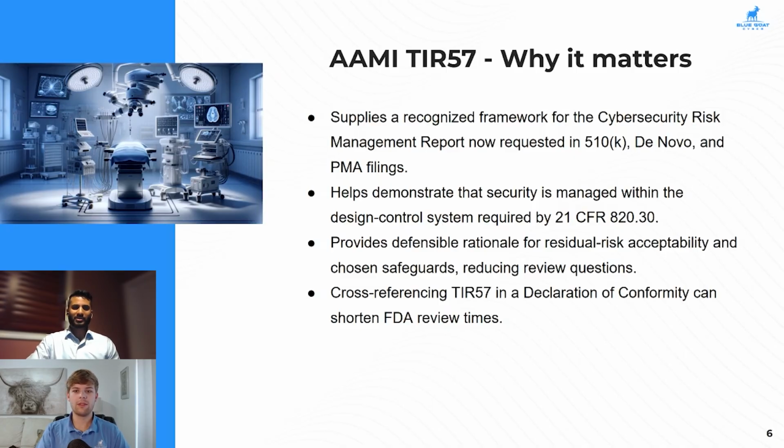Absolutely. And I think it's in a sense no different than all the other frameworks, in the sense that you need to start early on. You need to implement the risk analysis and risk assessment process right at the start of your design process. So again, it's not an afterthought. It's not something you come to at the end when you're about to submit to FDA and try to figure out your risks and risk assessment. So TIR 57, as Trevor has been mentioning, ties back to ISO 14971. We're all used to ISO 14971, the benchmark risk management standard for medical devices.